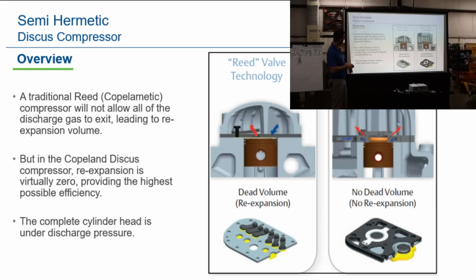With the Discus, there's virtually zero re-expansion of the gas. See right here? So the compressor cylinder head is under discharge pressure. So you've got to remember that as well. That whole head on the Discus is high pressure, hot gas. Everybody okay with that? Good.